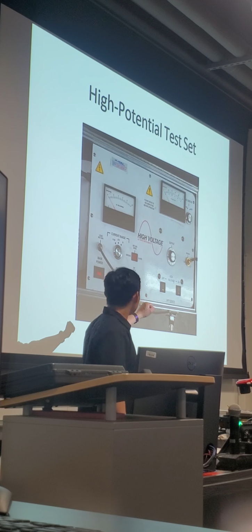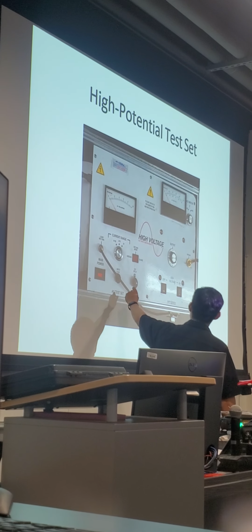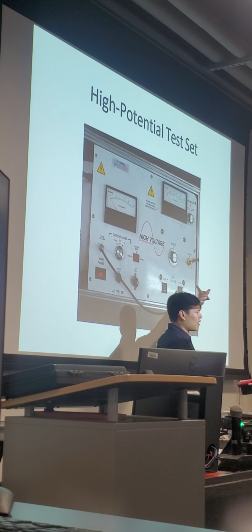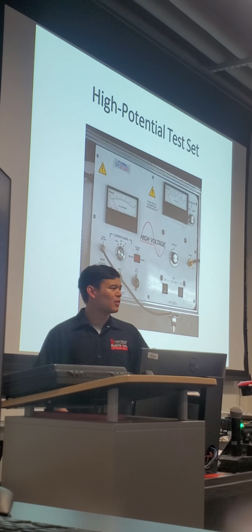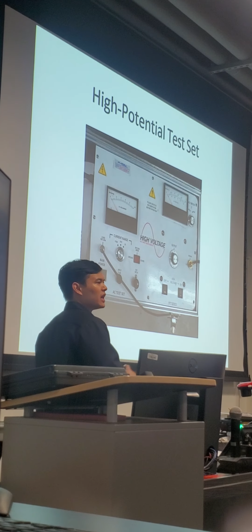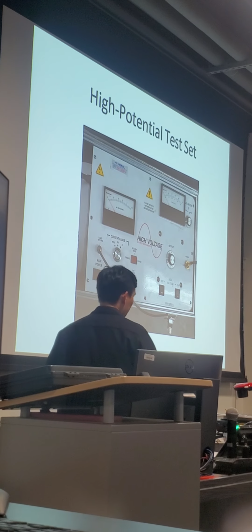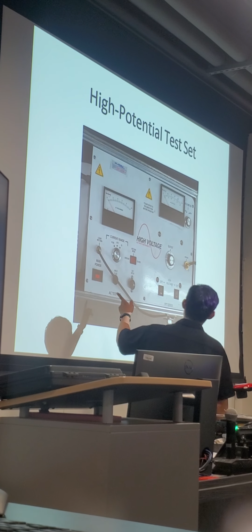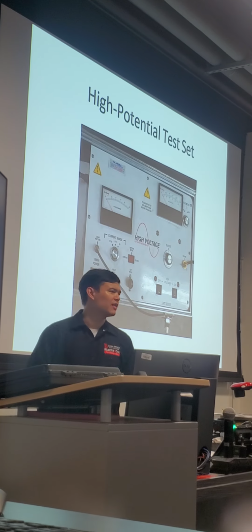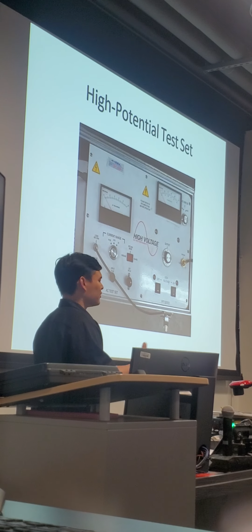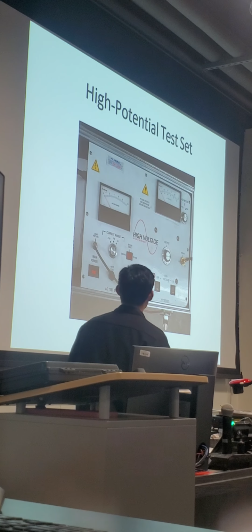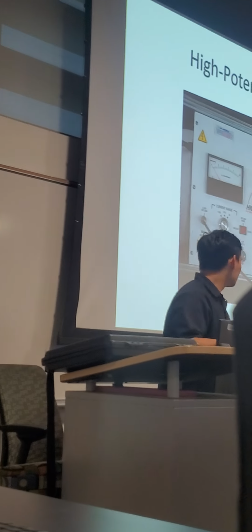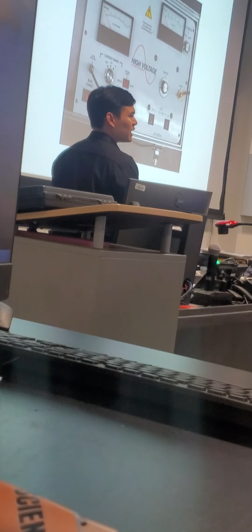I want to draw your attention to main power, our high voltage on and off, and then our output. That's three different ways in which we control energizing this equipment. For those of you who were here Tuesday, remember we want barriers of entry to guard ourselves from inadvertent energization, from accidentally hurting ourselves. If you bypass all three of these components in order to begin the test, then you know you're in control, and that you have specific intent to energize this circuit, especially to the tune of 28,800 volts.